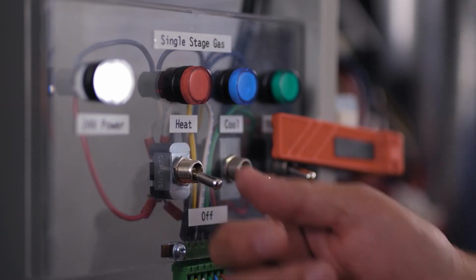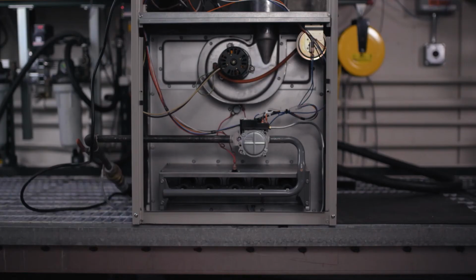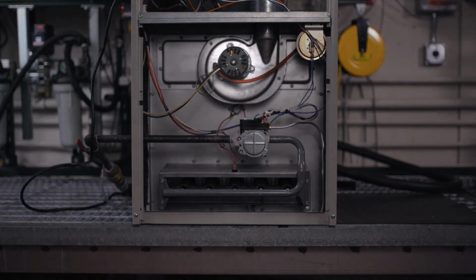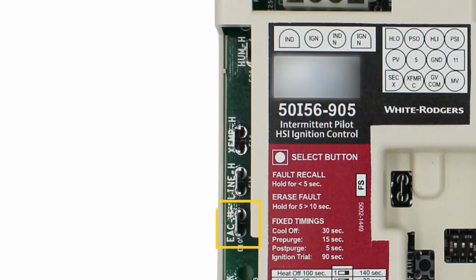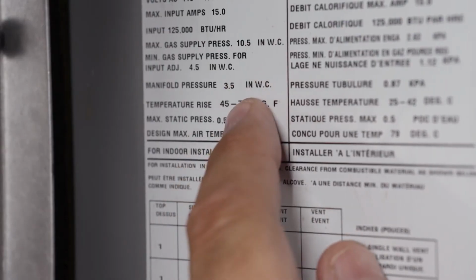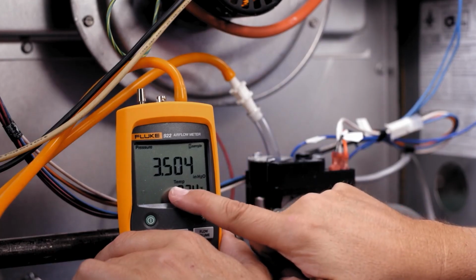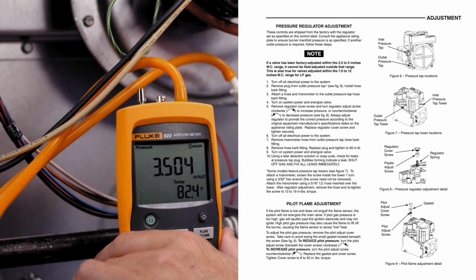To verify proper operation, make a call for heat. The normal sequence of operation is inducer blower and, if equipped, humidifier. Next, the pressure switch actuation, igniter warm-up, pilot valve, flame sensor, main gas valve, blower, and EAC if so equipped. Locate the gas pressure table on the furnace and adjust the pressure if necessary. To adjust, consult the gas valve installation instructions.